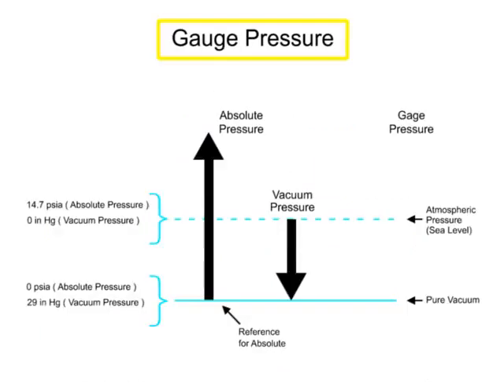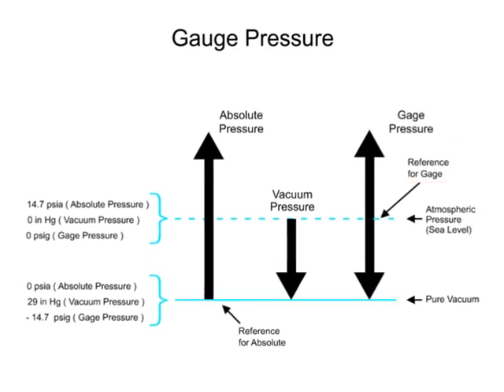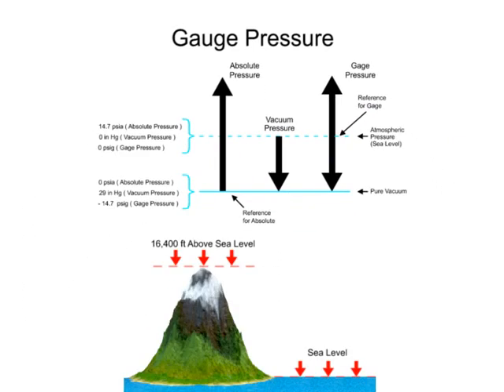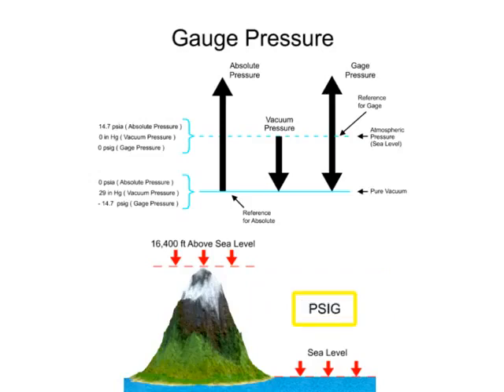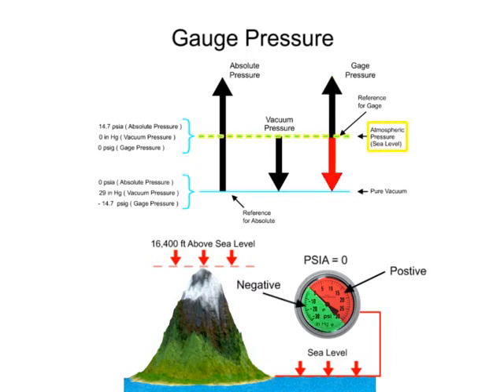Gauge pressure scale uses atmospheric pressure as the reference. The unit of measurement for gauge pressure is pounds per square inch gauge, abbreviated as PSIG. At sea level, the gauge measurement is 0. Measurement of gauge pressure can be positive or negative and is determined by whether it is above or below atmospheric pressure.